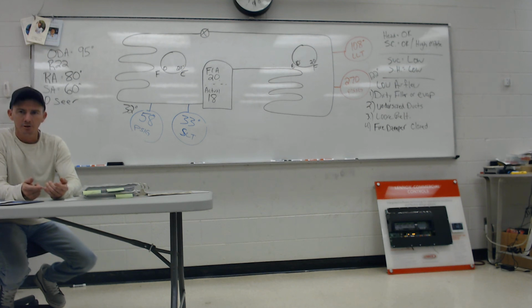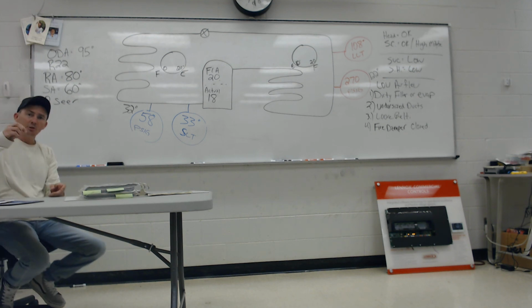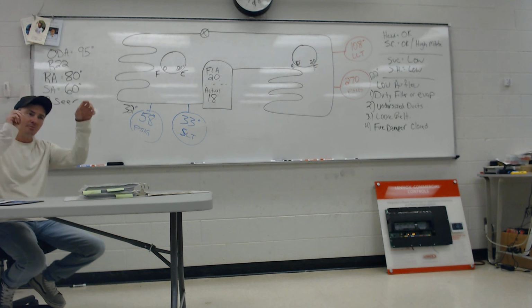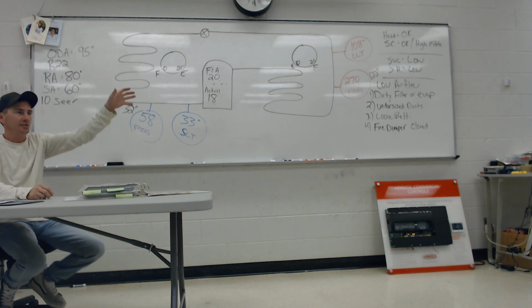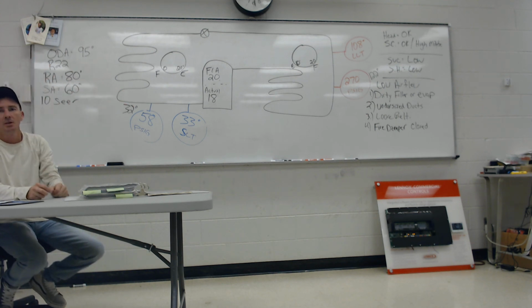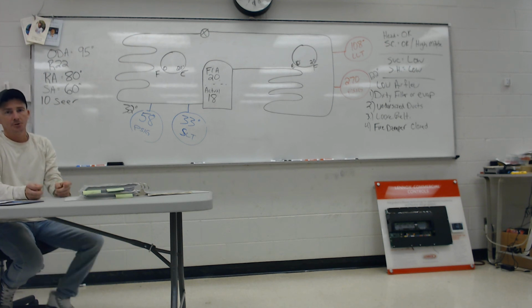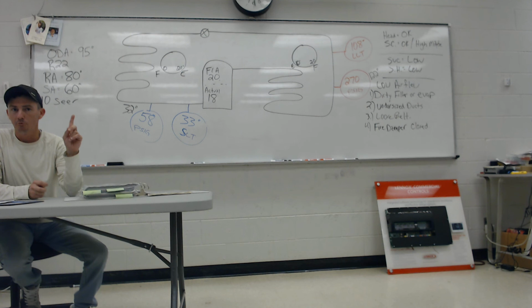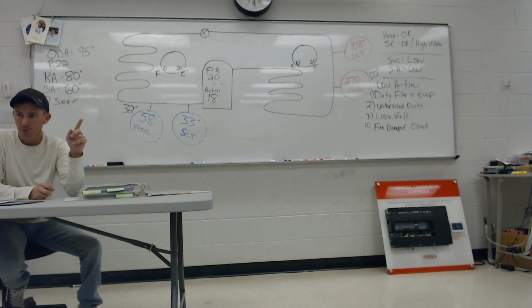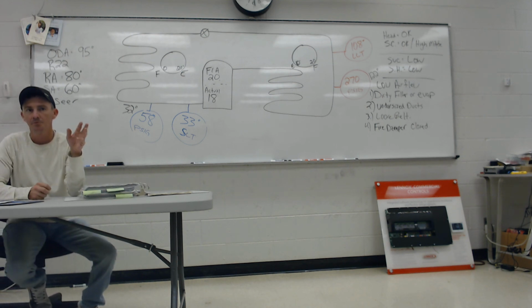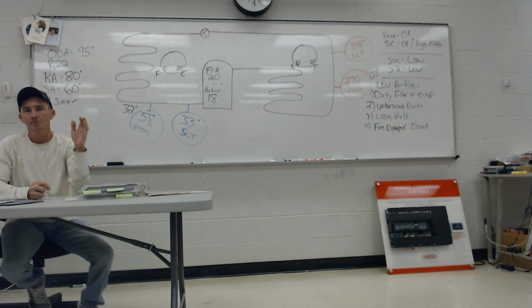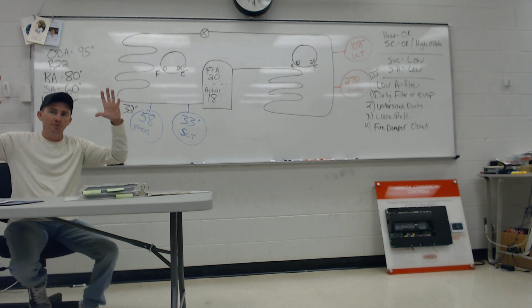Undersized ductwork. That cheat sheet I gave you, undersized duct. You can just look at the plenum and say, hey, it's got a 10-inch tap, an 8-inch tap, a 12-inch tap. I would just burn these in my head, hopefully if I'm you guys. A 10-inch will move 1 ton. A 10-inch moves 400 CFM, roughly. So 10-inch is 400.